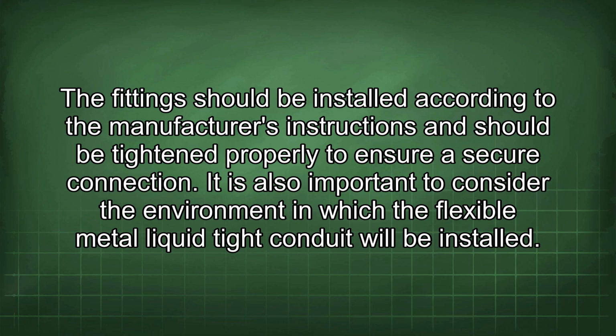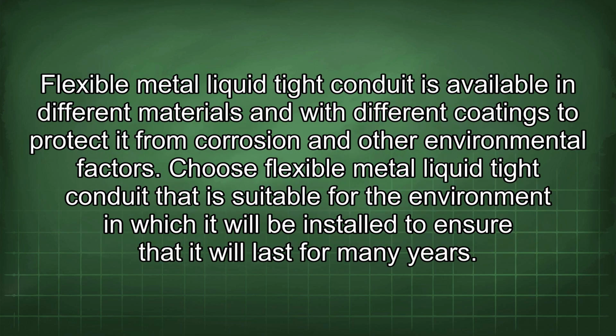ensure a secure connection. It is also important to consider the environment in which the flexible metal liquid tight conduit will be installed. It is available in different materials and with different coatings to protect it from corrosion and other environmental factors. Choose flexible metal liquid tight conduit that is suitable for the environment in which it will be installed to ensure that it will last for many years.